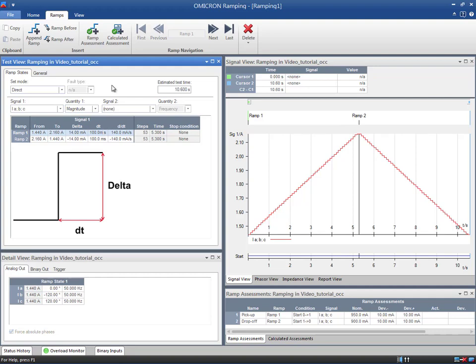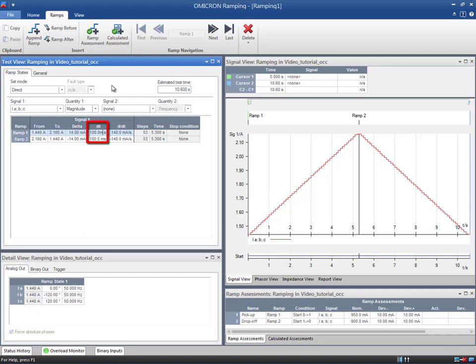The time is the period between two ramp steps. This duration must be longer than the operating time of the relay. Since the pickup is estimated by the relay's manual to be 30 milliseconds, the step time has to be greater than this value. Therefore, 100 milliseconds will suffice. We apply the same settings for the second ramp.